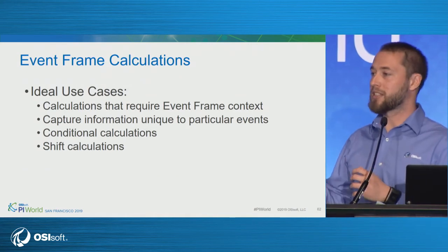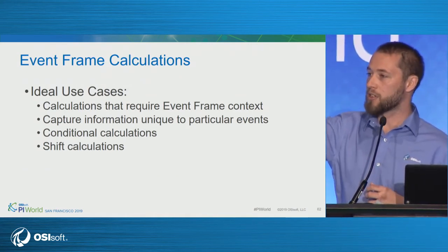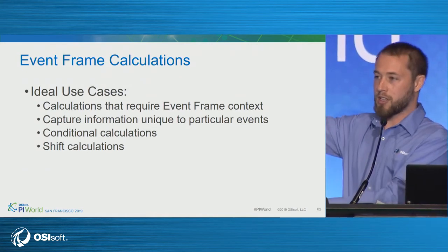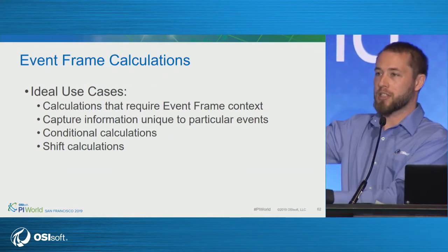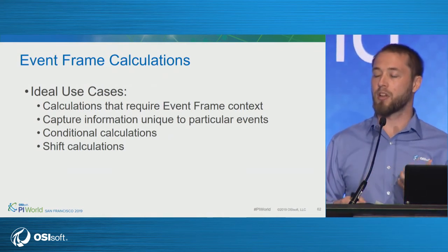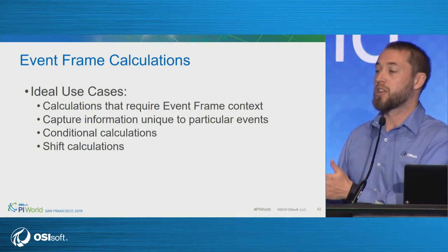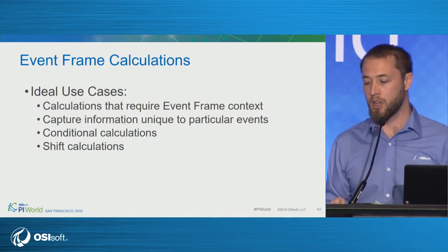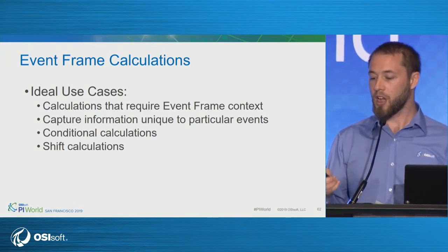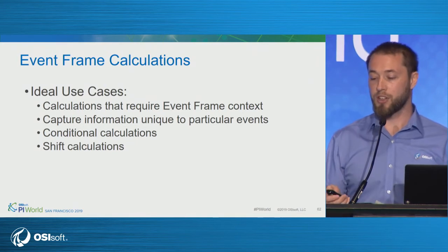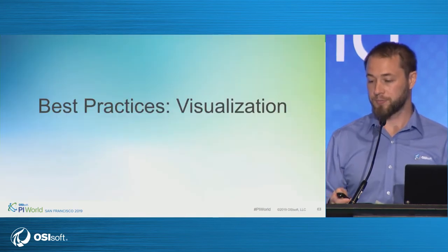So it might not make sense to put this analysis on the element because then you'd always be running this calculation. It makes a little bit more sense to put it on the event frame, as then it only runs within the context of that event frame. And this is ideal also for conditional calculations and shift calculations.